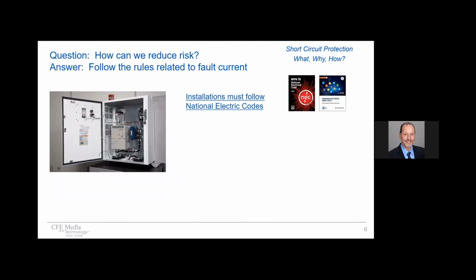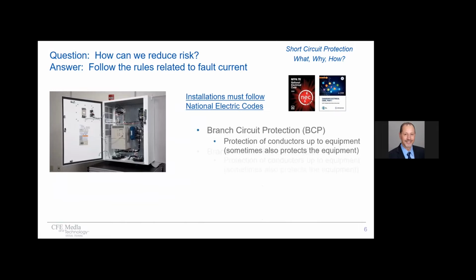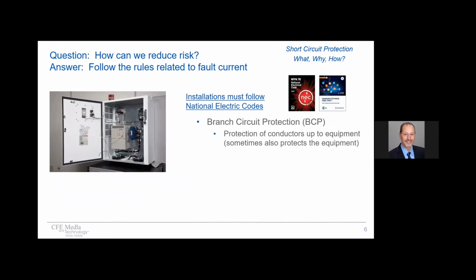Well, complete elimination of danger is near impossible for most things in life, but we can certainly greatly reduce risk. Fortunately, there are helpful rules to follow. Most installations are subject to national electric codes, such as the NEC for the US and the CEC for Canada. And these codes specify that you must protect your branch circuits. And so that's branch circuits or wiring up to the equipment. And in some cases, it also protects the equipment.